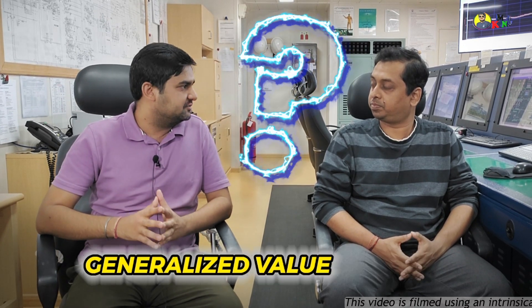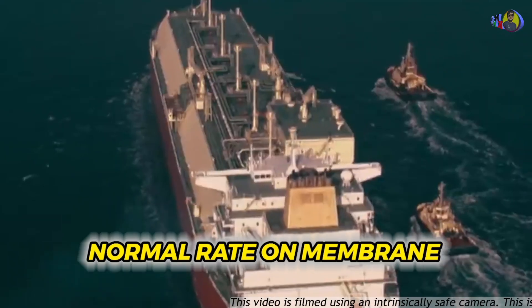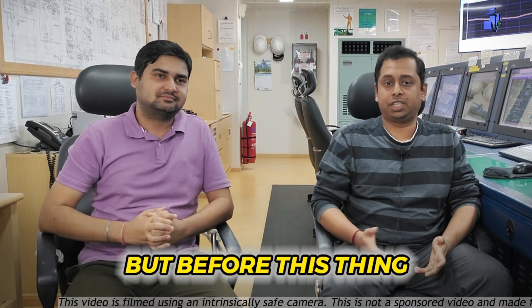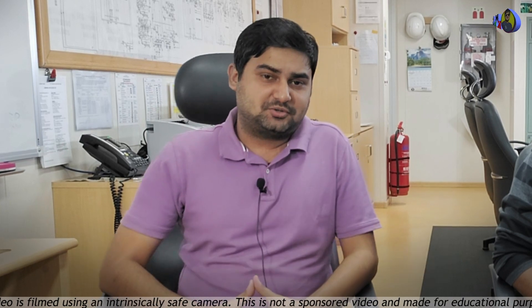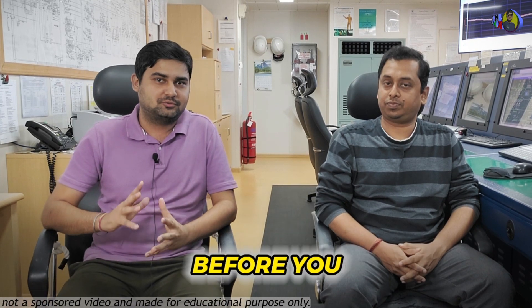Regarding the average rate of cooling down, cool down is mainly done as per the table, but the normal rate on a membrane ship is minus 20 degrees per hour, and for Moss type it is minus 10 degrees per hour. As a disclaimer, always refer to your ship's specific tables as well, just to be on the safer side before commencing cool down.